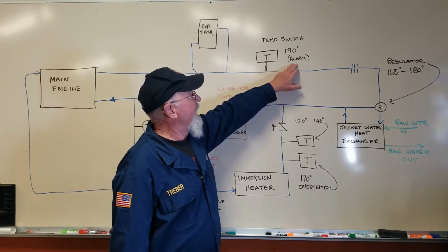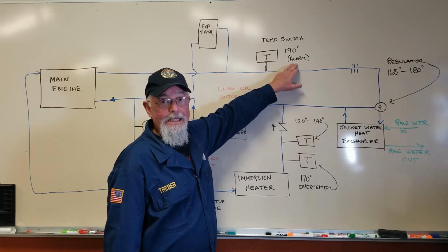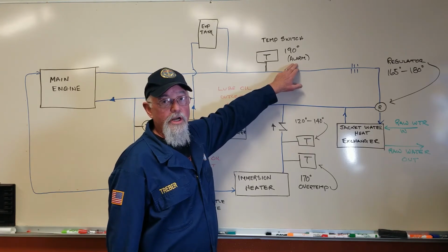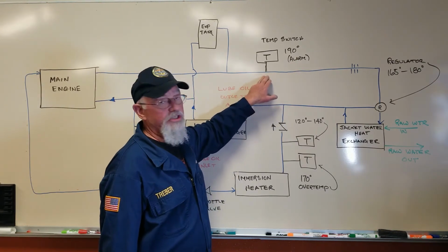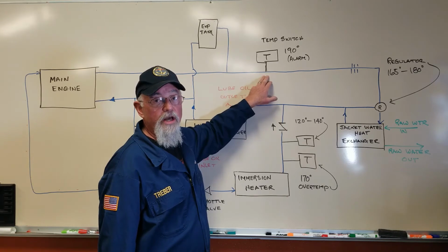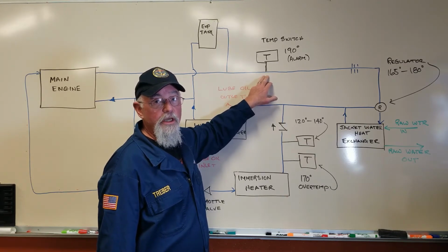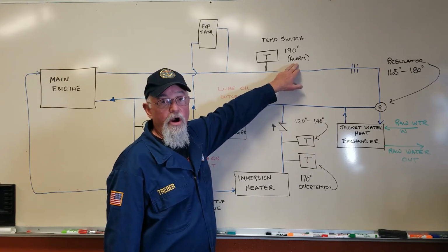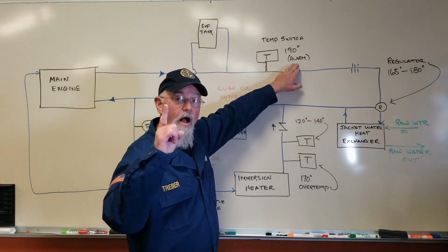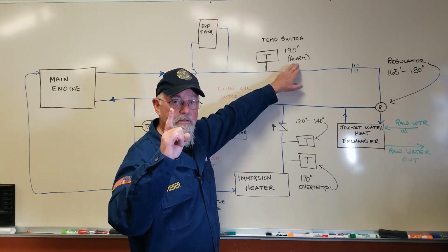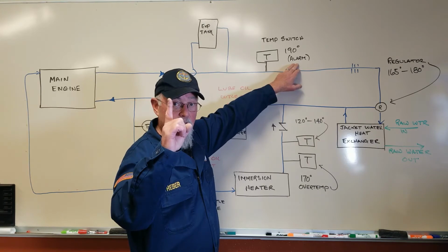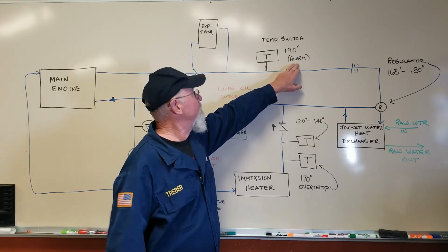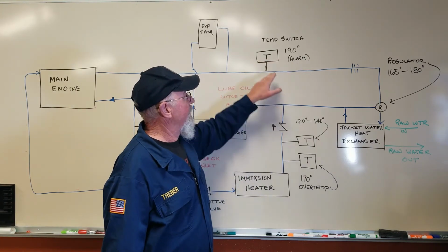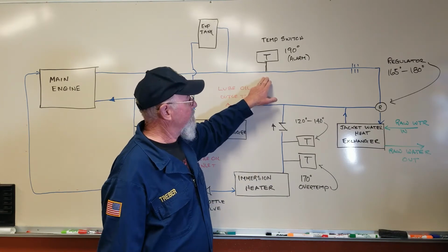So it is set for 190 degrees, which means during normal operation, if the engine's jacket water temperature reaches or exceeds 190 degrees, you will get a high jacket water alarm. That's one of the alarms on the main engine's alarm panel. There's one of them, right? There's more than one. So that's a temperature switch, and it's just sensing the temperature of the jacket water.